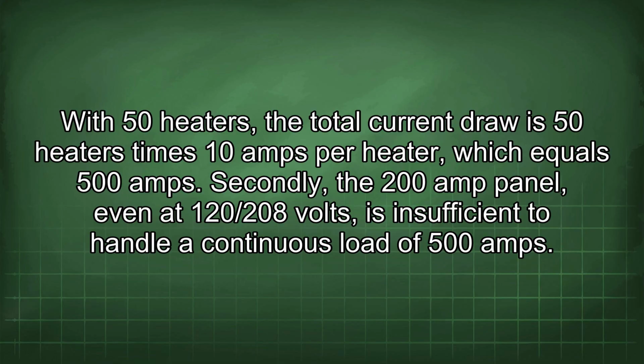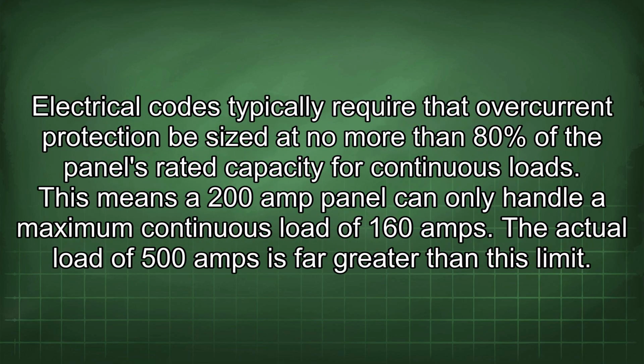Secondly, the 200 amp panel, even at 120/208 volts, is insufficient to handle a continuous load of 500 amps. Electrical codes typically require that overcurrent protection be sized at no more than 80% of the panel's rated capacity for continuous loads. This means a 200 amp panel can only handle a maximum continuous load of 160 amps. The actual load of 500 amps is far greater than this limit.